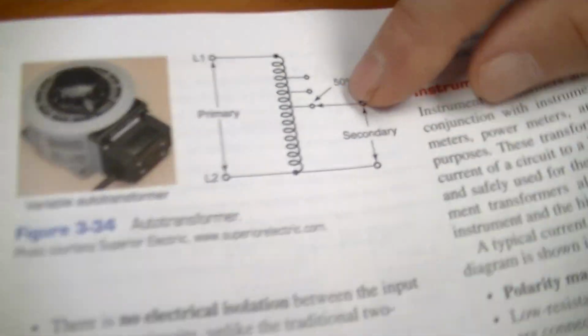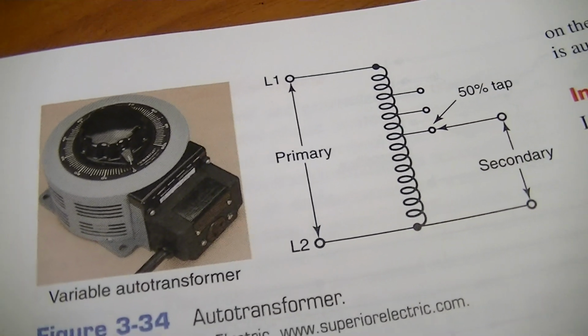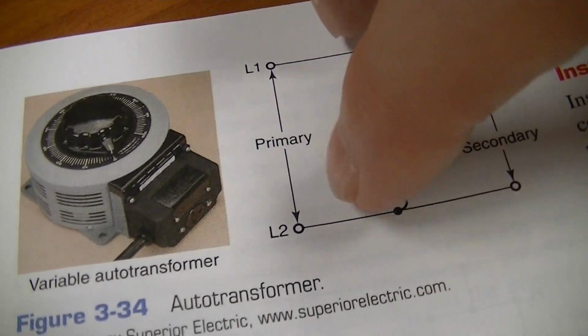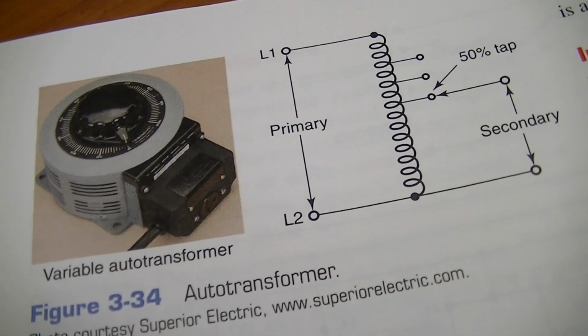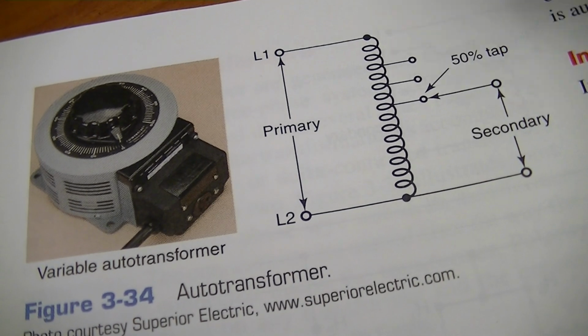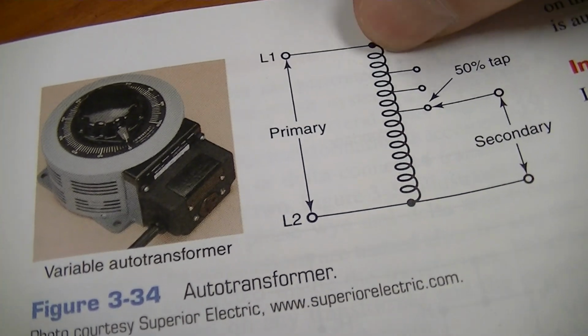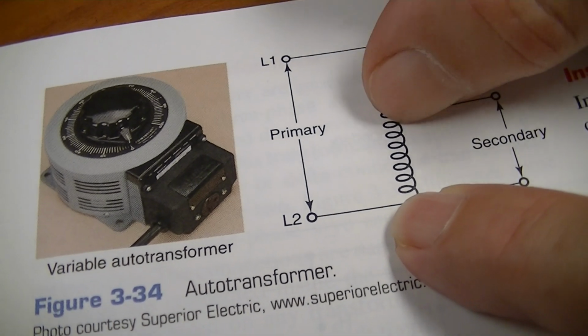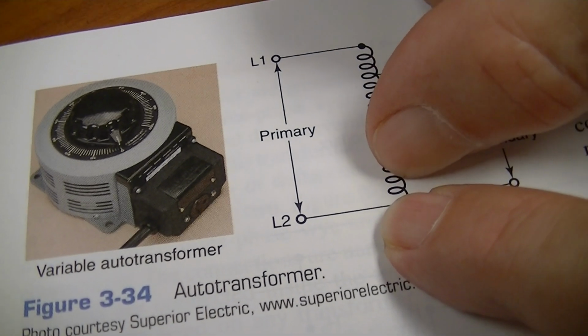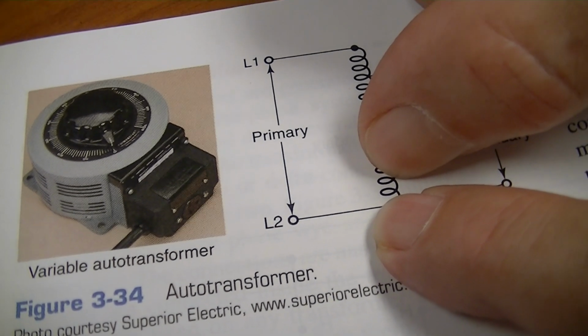Now, let's talk about the auto transformer. All right, the auto transformer, I just happen to have one here, but that's okay. Basically, if you look at that picture, and as you would, it has a single coil. It doesn't have two coils, it only has one. The primary is coming in and energizing the whole coil. Well, think of it as running your thumb up, keeping your one finger down there and running your thumb up and stopping wherever you want. The more coils you're cutting, the more voltage you're getting.